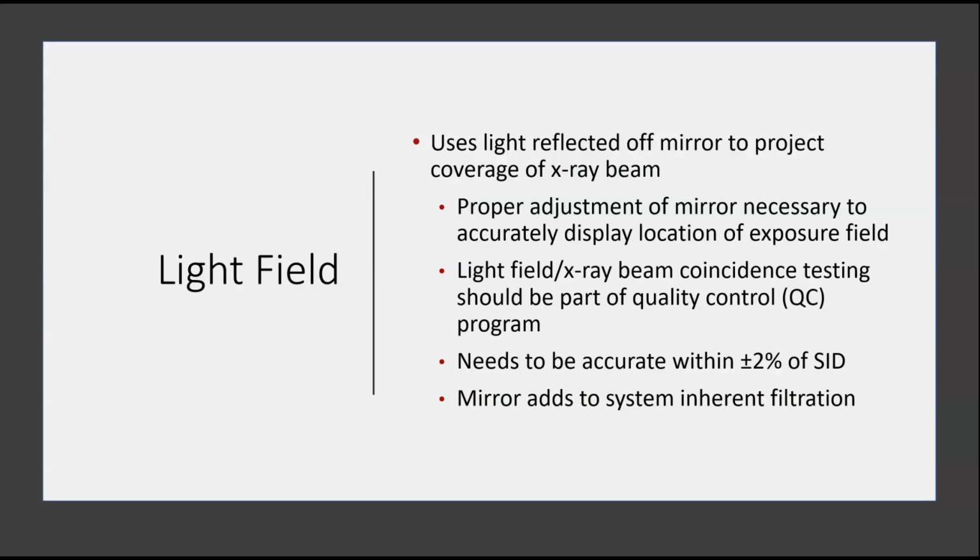So your light field uses the light reflected off a mirror to project coverage of the X-ray beam. So proper adjustment of the mirror is necessary to accurately display the location of your exposure field. So the light field / X-ray beam coincide testing should be part of the quality control program. So this actually has to be tested. It needs to be accurate within plus or minus 2% of your SID. So the mirror also adds inherent filtration, and we've covered that already.